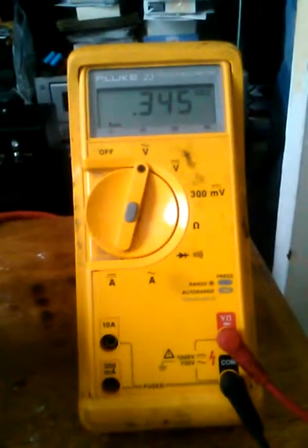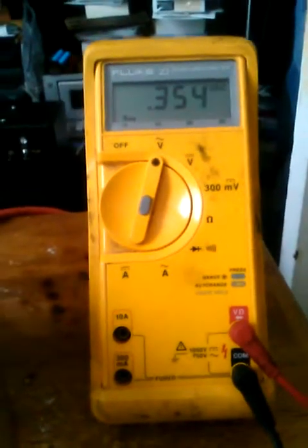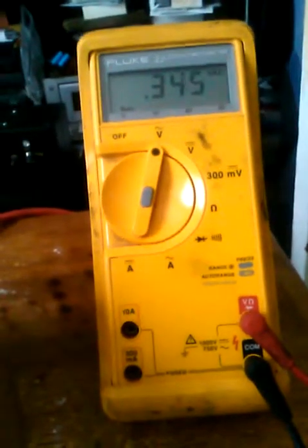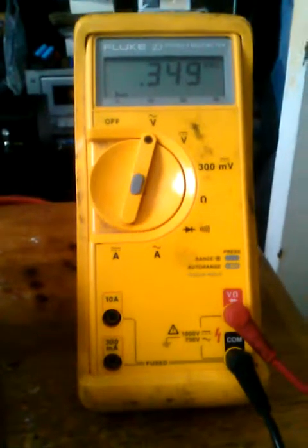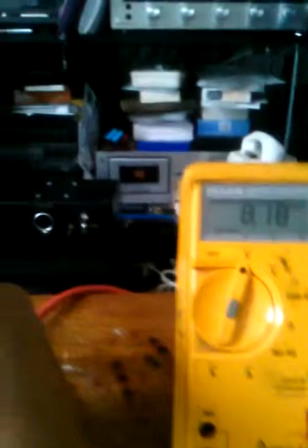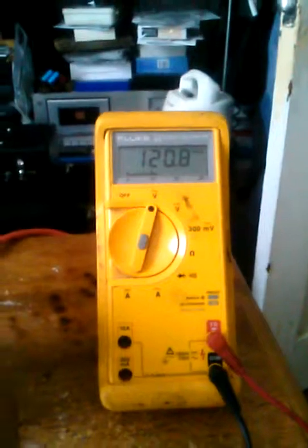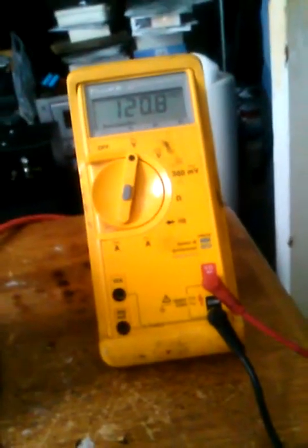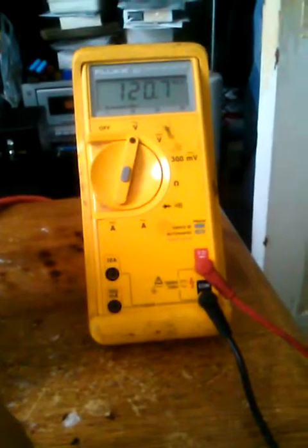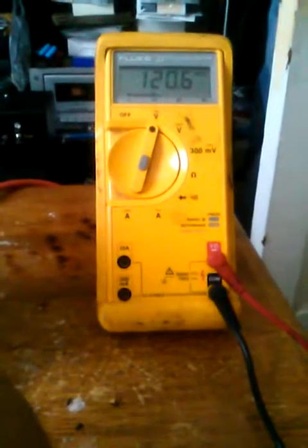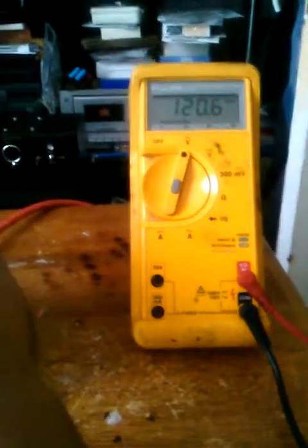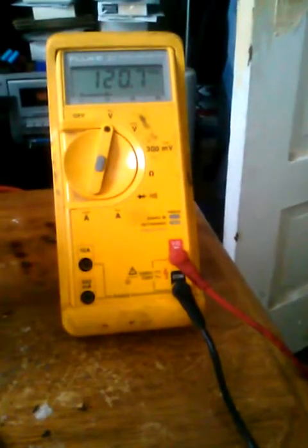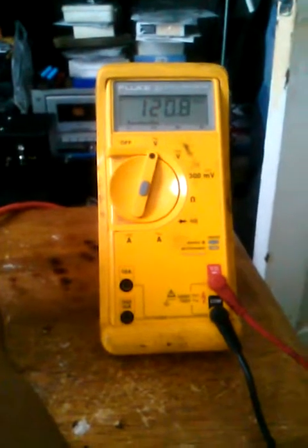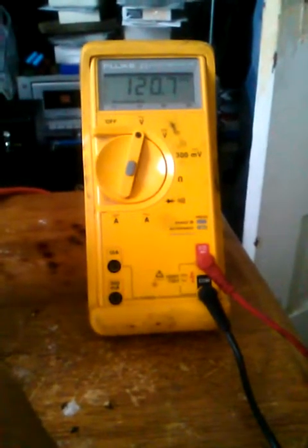Which means if something happens to your electrical outlet and it needs something to go back to ground, the path of least resistance, which is your ground circuit, and if anybody who's an electrician can correct me on the terminology, that would tell you that you need a properly grounded outlet, so that if a short was to occur at the outlet, it should go back to ground and trip the breaker, like a circuit breaker is supposed to. If it doesn't trip the breaker, that means you have a problem somewhere with your circuit breaker or the switch on the panel, and you may need an electrician to correct that issue as soon as possible before continuing, because anything else could damage your components and possibly cause a fire or other electrical damage to your panel, which can be costly to repair.